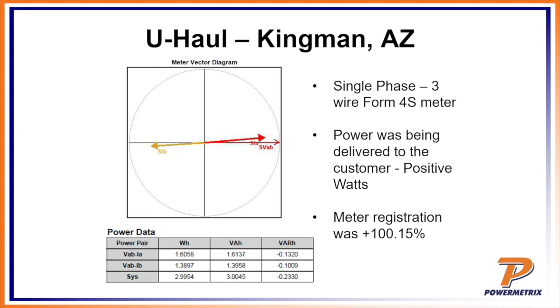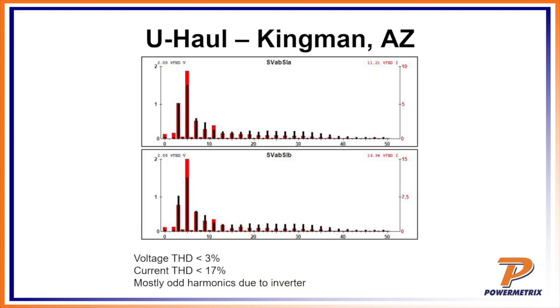And when it went to delivered mode, you can see that it kind of shifted right back, and then we got positive registration. This is very common. When you start getting into the harmonics, current harmonics are going to be high. Over 20% is going to be pretty common, so don't get too worried about that. That's just the technology that you've got out there.